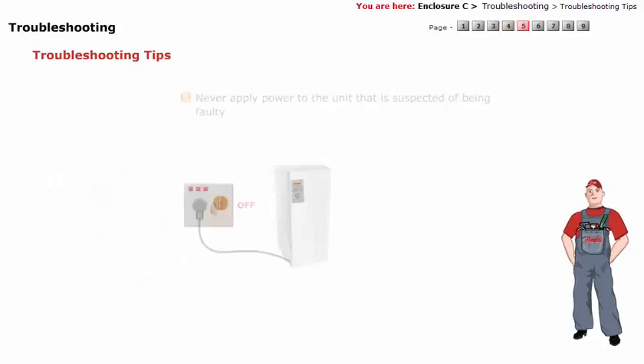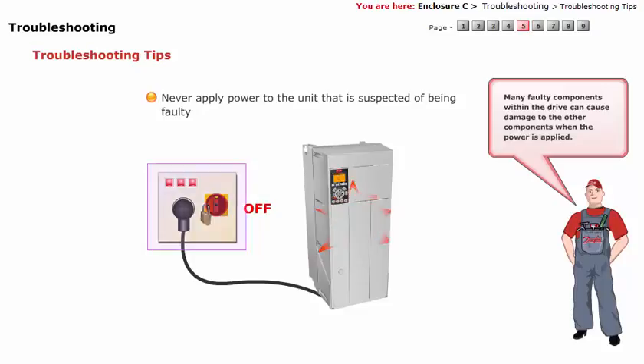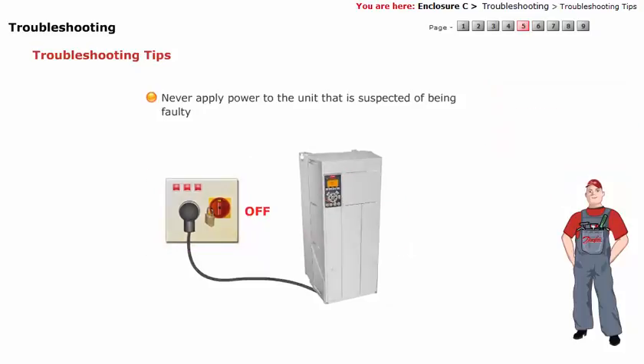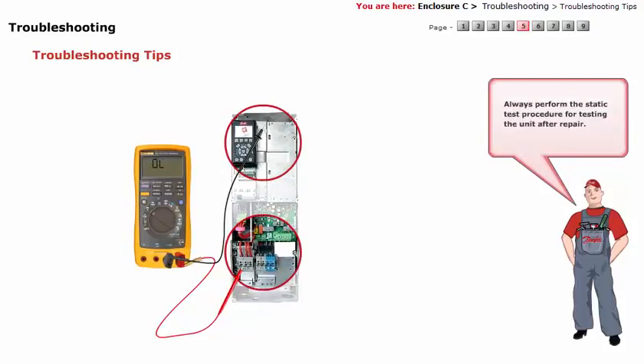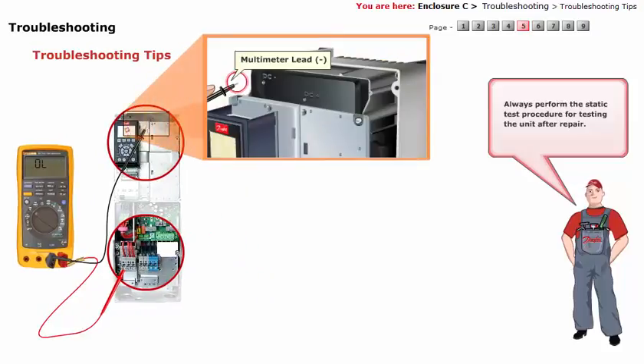Tip 2: Never apply power to a unit that is suspected of being faulty. Many faulty components within the drive can cause damage to other components when power is applied. Always perform the static test procedure for testing the unit after repair.